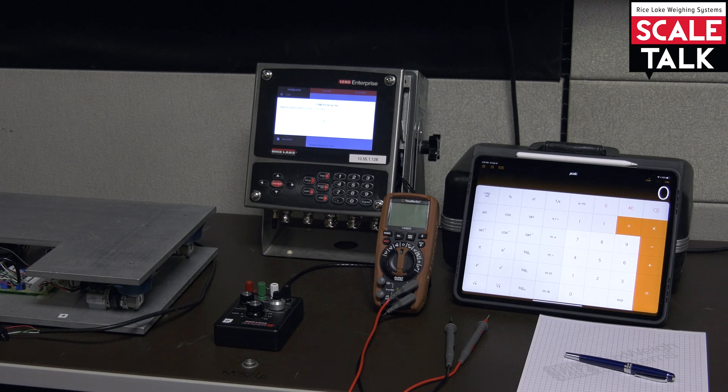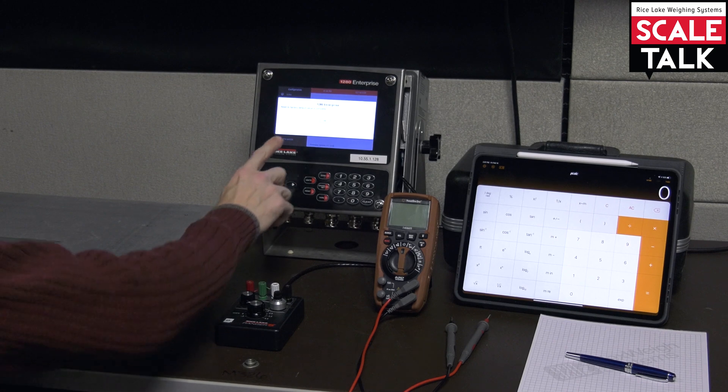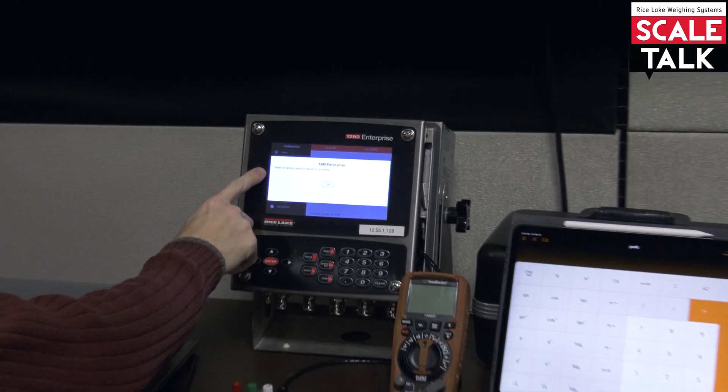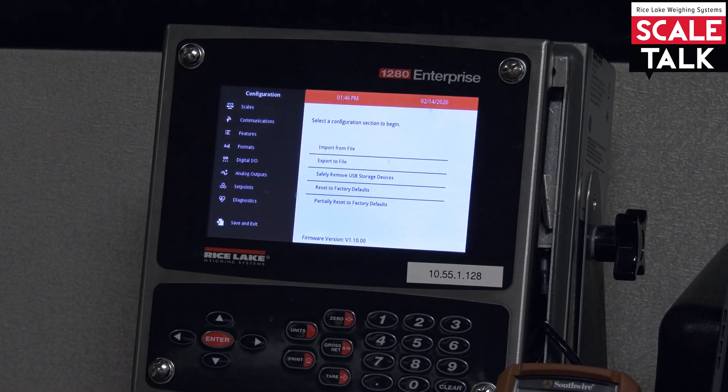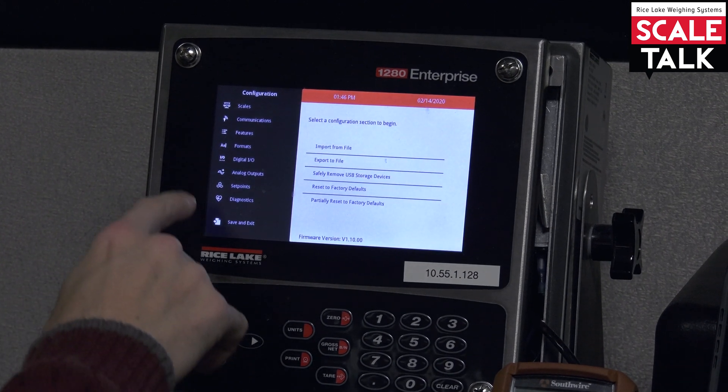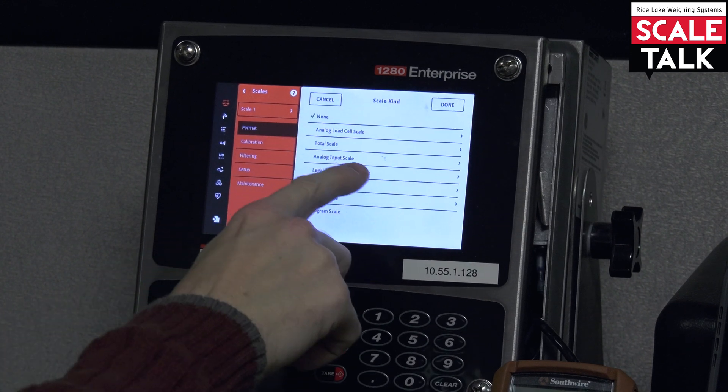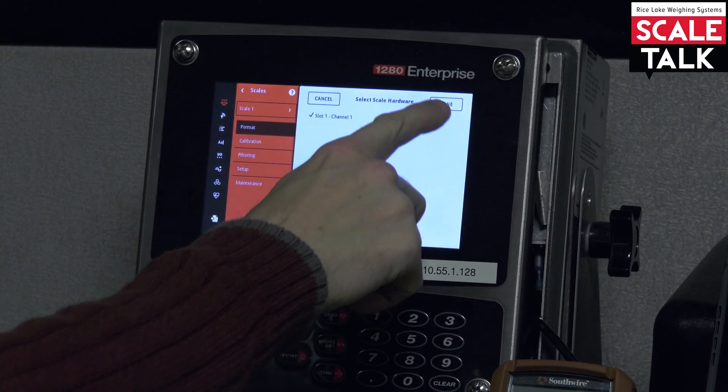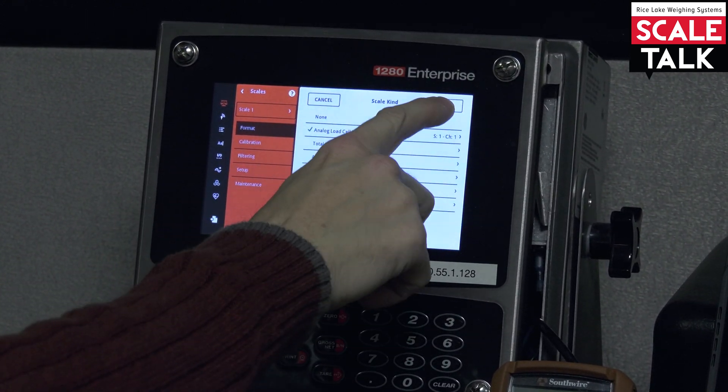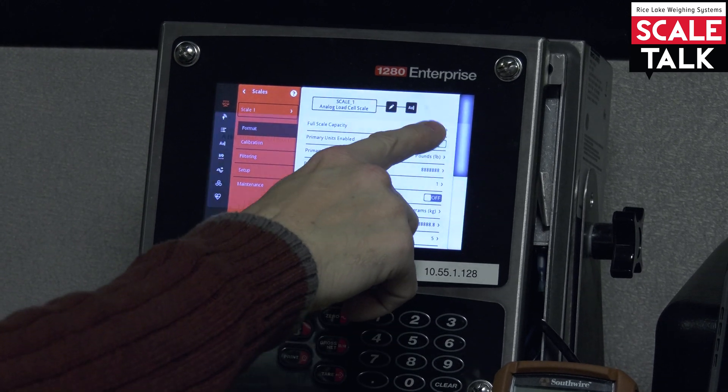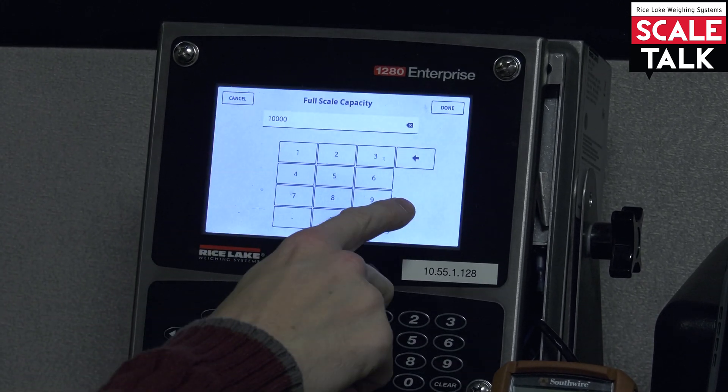So what we've got here, let's go through this. We've got our 1280 here and we're going to start at a default situation just so we know that it's not currently calibrated. That means we'll have to go in and set up our scale. This is going to be a 50 pound scale.